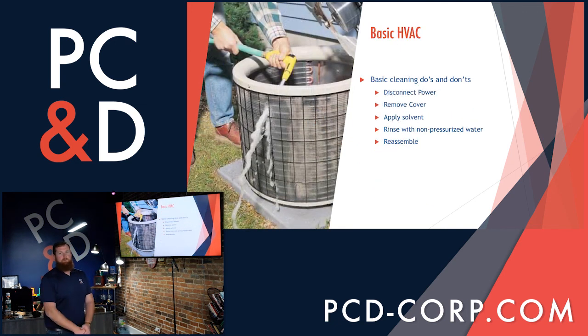All right, now with the kitchen out of the way, we can go over to our HVAC equipment. A lot of you have various pieces of HVAC equipment. Most typically, you'll have your split systems, which is depicted here. And I'm going to walk you through the basic do's and don'ts of cleaning the HVAC system, or also the condenser outside. So obviously, the first thing we want to do is disconnect the power. That's typically located right next to the condenser itself, either by a throw switch or a removable fuse, at which point all you need to do is throw it to the off position or remove the fuse entirely.